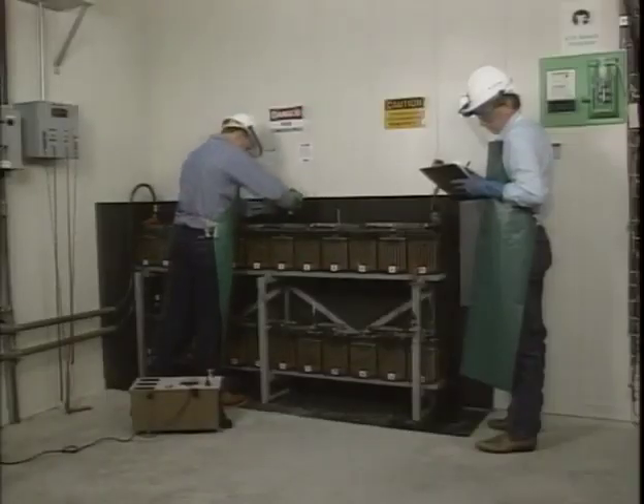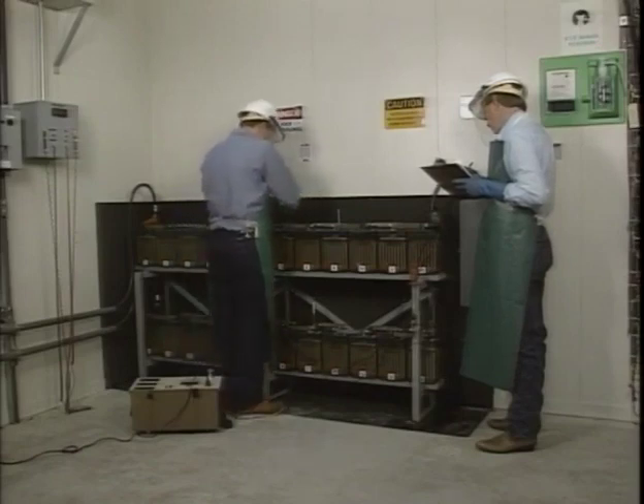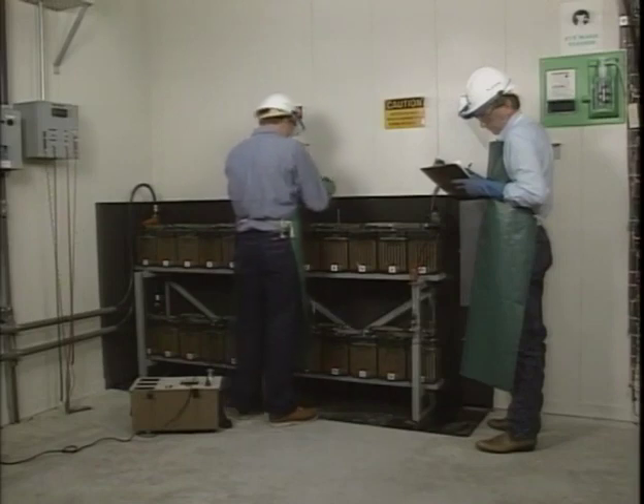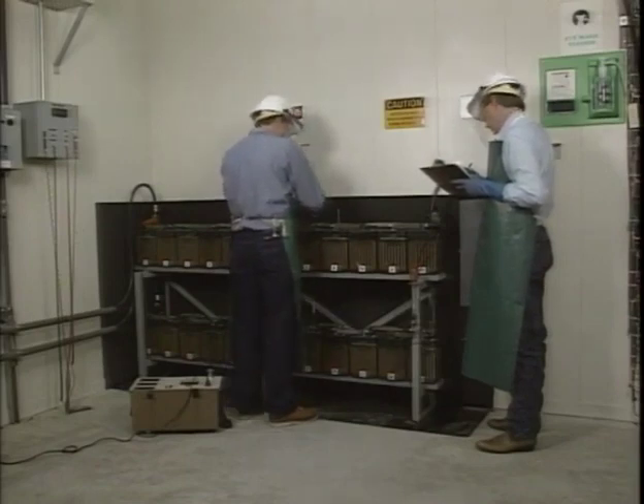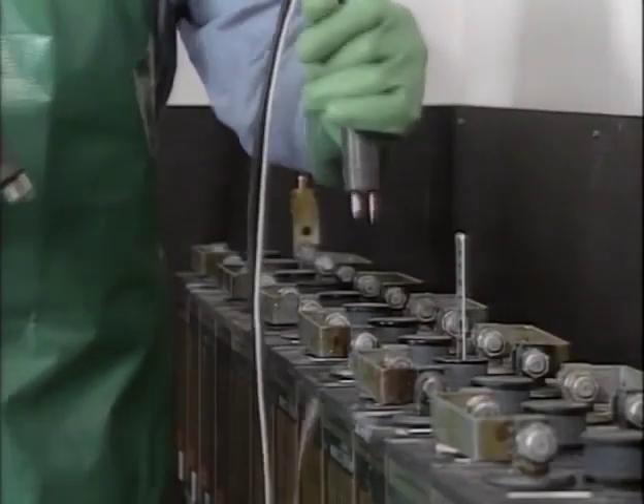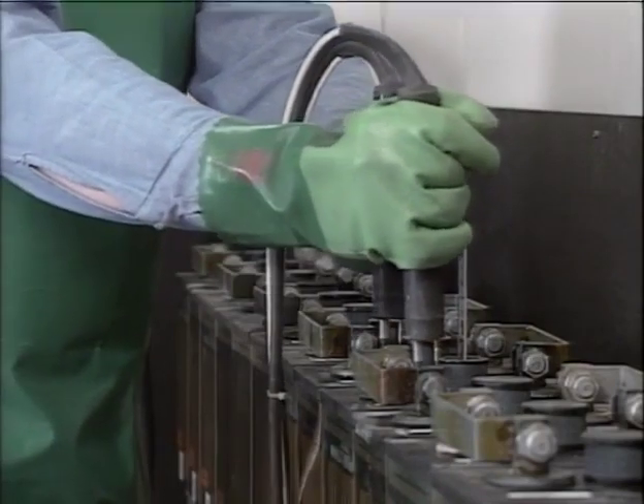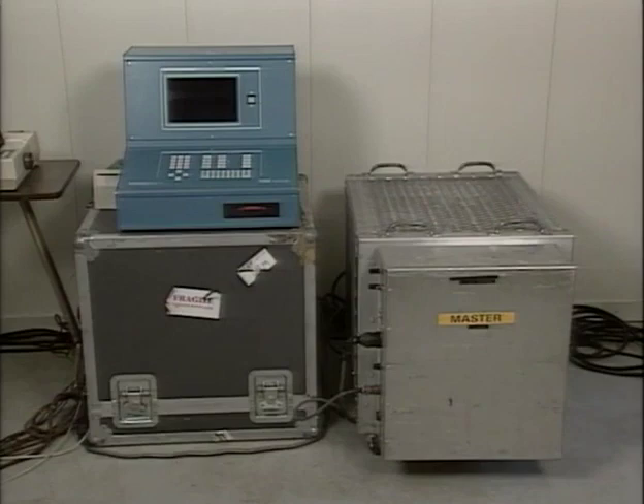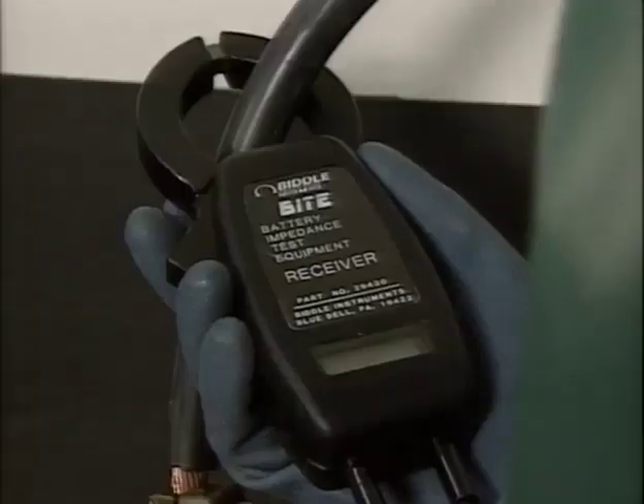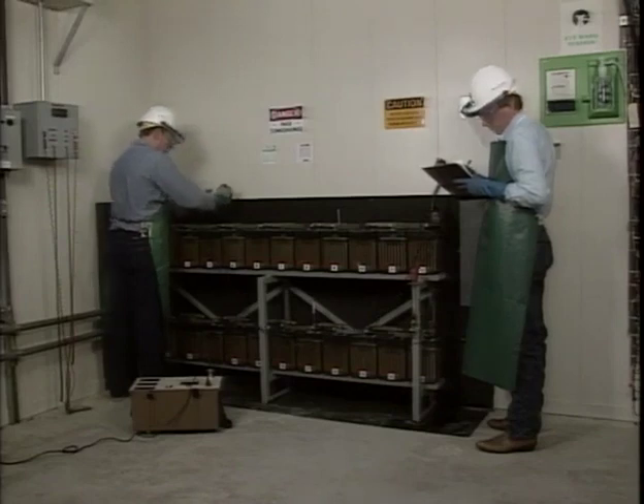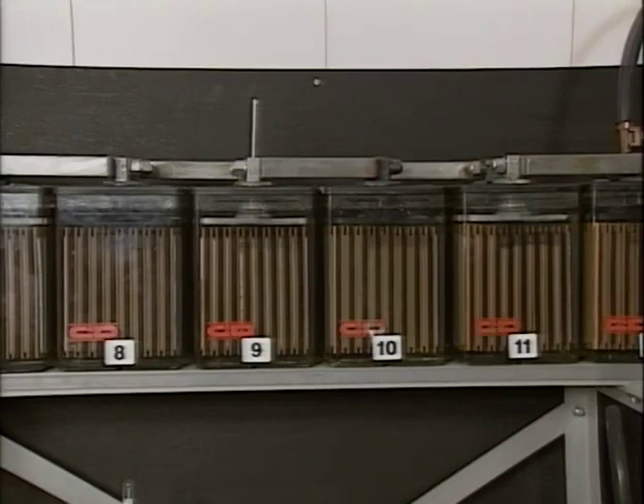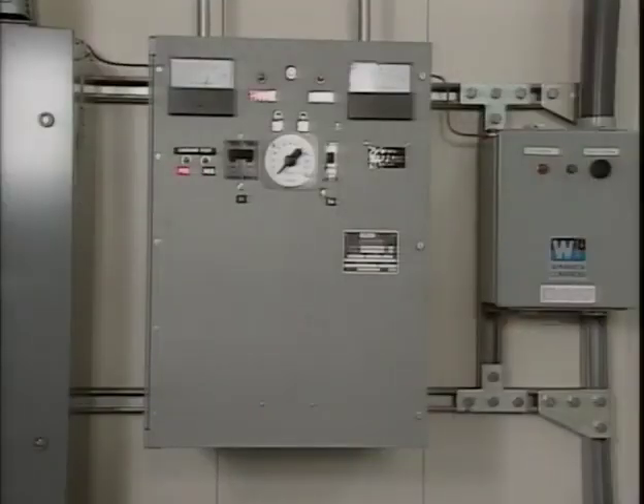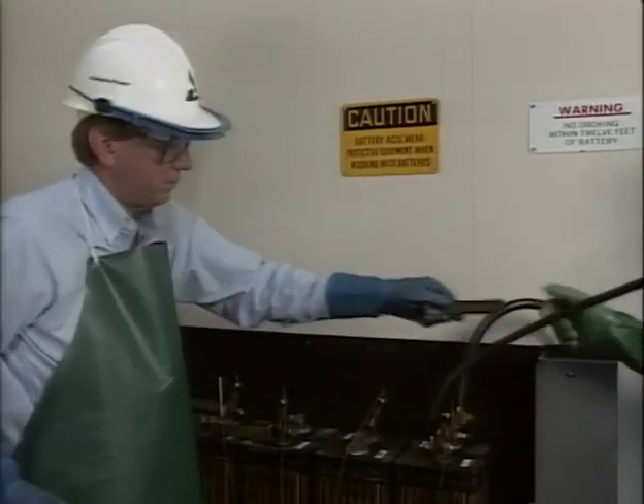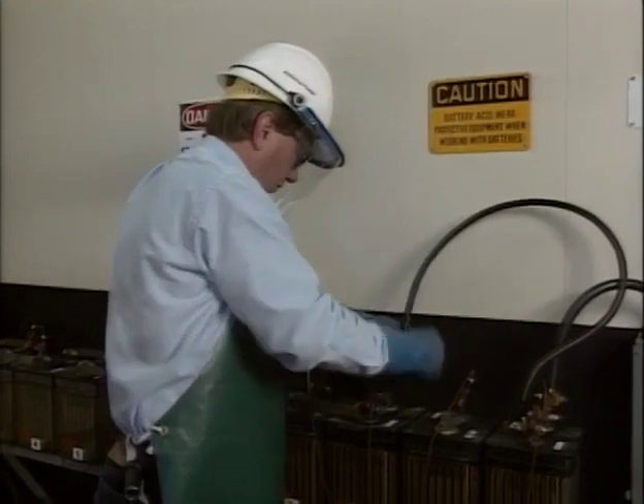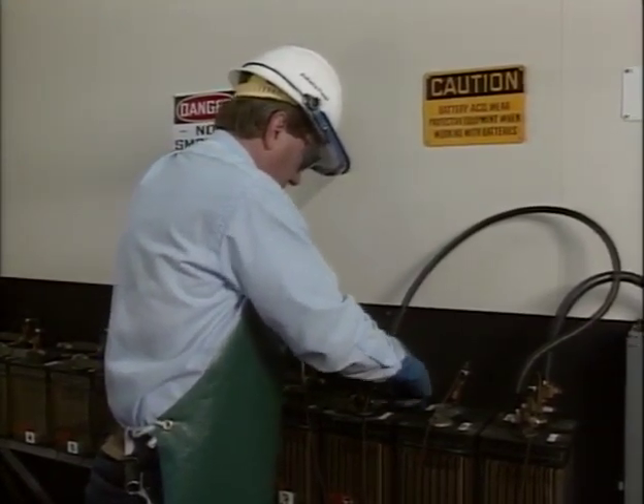The unfailing operation of a substation battery is crucial to the protection and control of substation equipment and transmission and distribution systems. The tests described in this program help to ensure that the battery is capable of performing its function. The tests described in this program include voltage and resistance testing, specific gravity testing, integrity and capacity testing, and impedance testing. This unit on substation battery testing, together with the units covering substation batteries and substation battery chargers, provide a solid foundation for the maintenance and testing you perform on your substation's batteries and battery chargers. To complete your training in substation battery systems, you may want to continue your training by learning about substation battery, cell, and charger replacement.